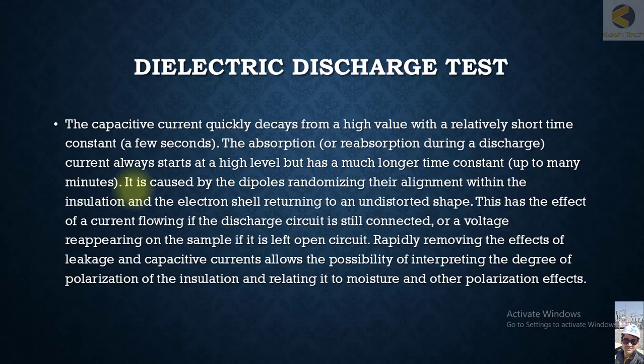The capacitive current quickly decays from a high value with a relatively short time constant of a few seconds. The absorption or reabsorption discharge current always starts at a higher level but has a much longer time constant — up to many minutes. It is caused by dipoles randomizing their alignment within the insulation and the electron shell returning to an undistorted shape.